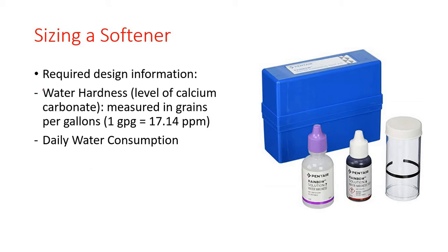The first information is the water hardness, which is the level of calcium carbonate in the water. This is measured in grains per gallon. We know that one grain per gallon is equivalent to 17.14 ppm, which is important for the conversions and calculations later on.